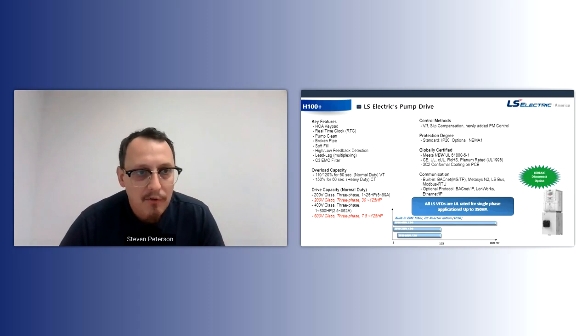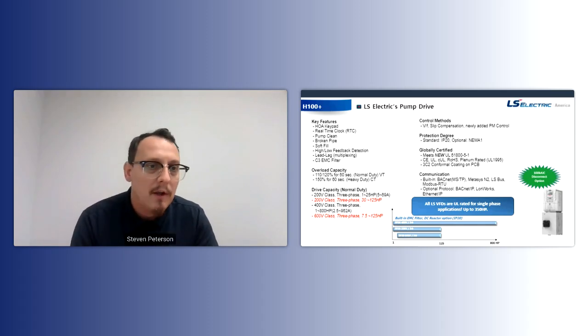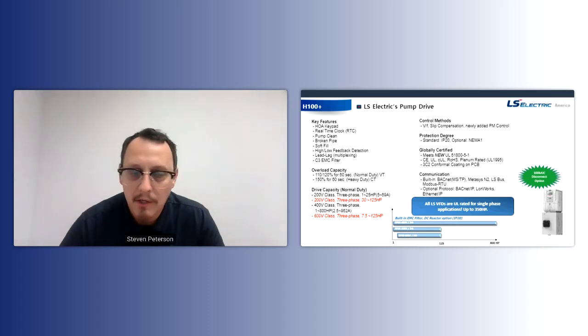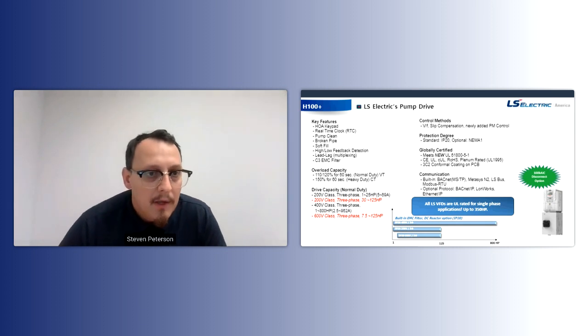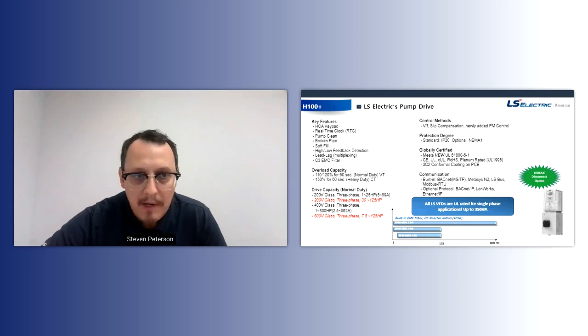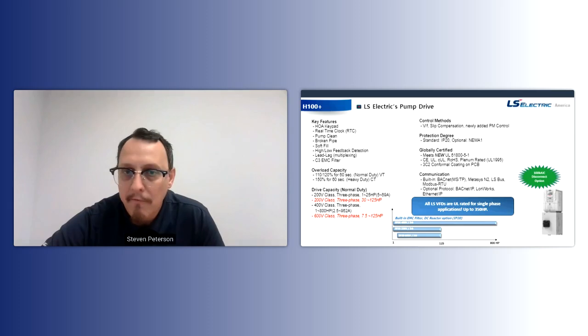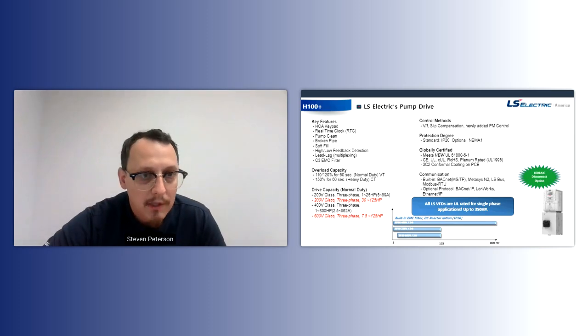I'm choosing to talk about the H100 Plus because there's a lot of pump jargon in there. It's directed towards the US market, so there's a lot of easy things in there to do the programming, and that's what we're going to be jumping into. So I hope at the end of the session you guys see that it really is that easy to program this drive. As mentioned, the H100 Plus is the series for pumping. It has an HOA keypad on it, so it does have a hand-off-auto keypad. You're going to see some close-ups of that hand-off-auto keypad coming up shortly.